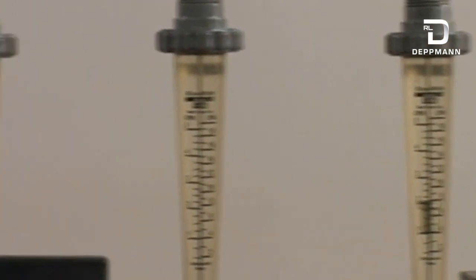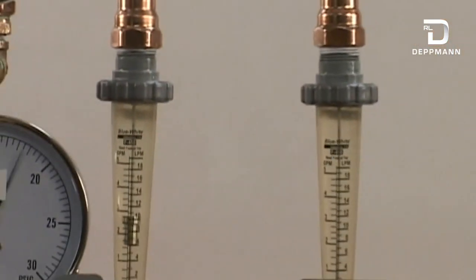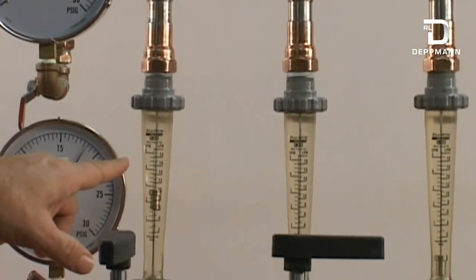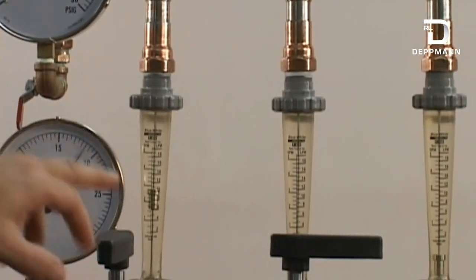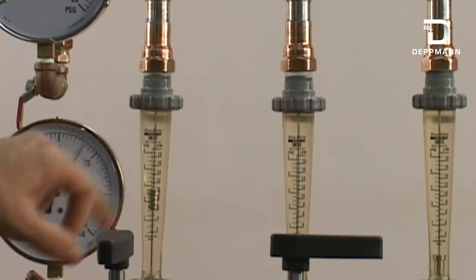Here, our pressure independent control valve is set for 3 GPM. So no matter what else goes on in the system, this is only going to allow 3 GPM through this zone.